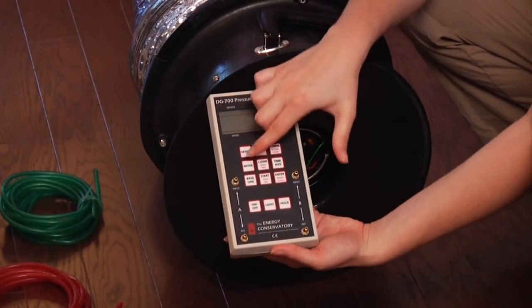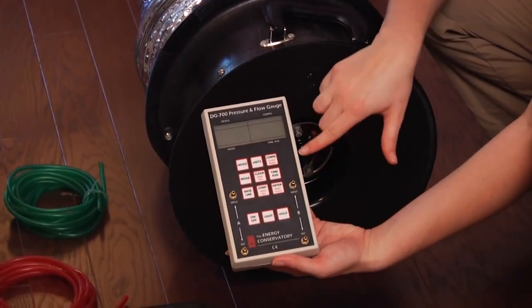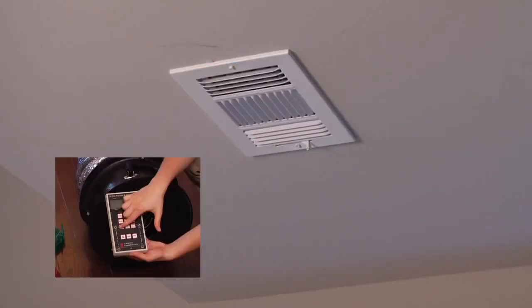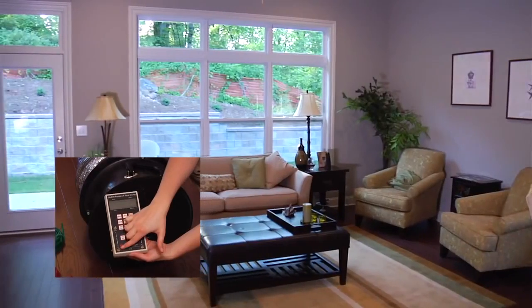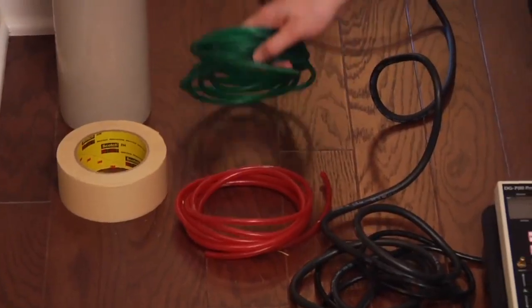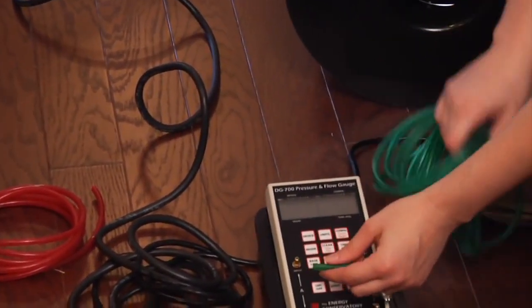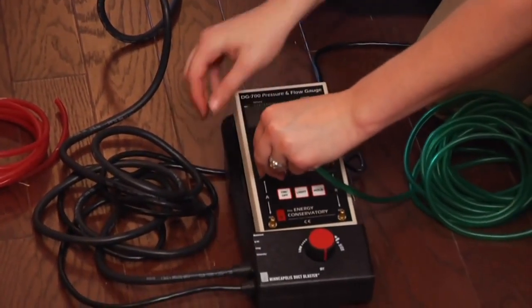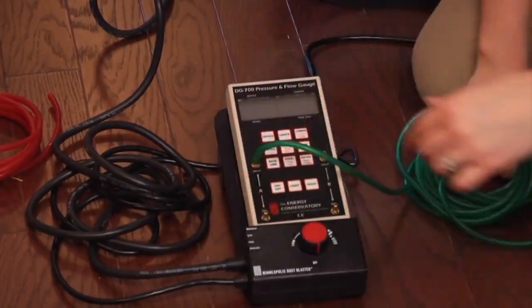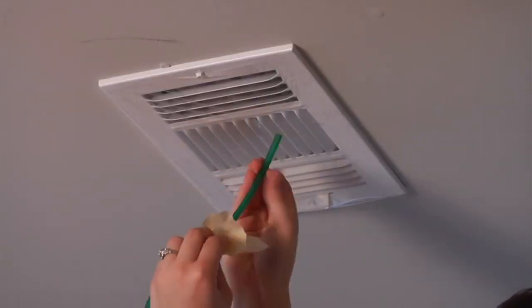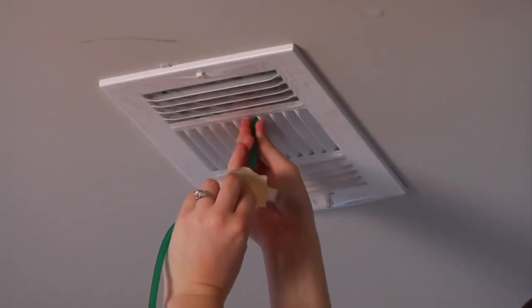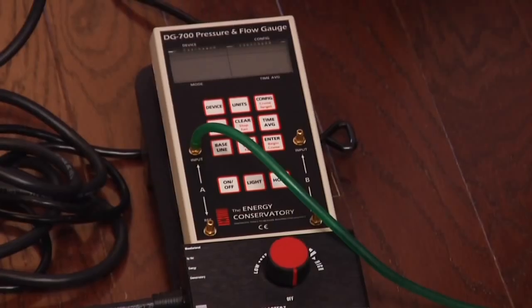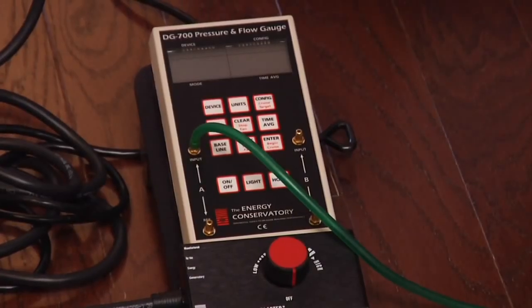The digital gauge has 2 sides and each side is a separate pressure gauge. Each pressure gauge measures the pressure difference between 2 taps. The A side will measure the pressure difference between the duct system and the house. To measure the pressure of the duct system, attach the green tube to the upper input tap on side A of the gauge. The other end of the green tube will run to a supply register. The lower reference tap needs to remain open to the house.